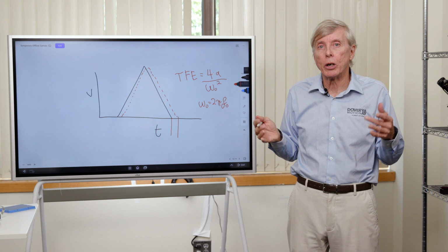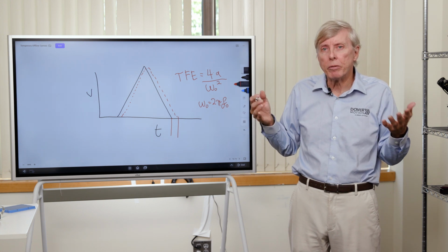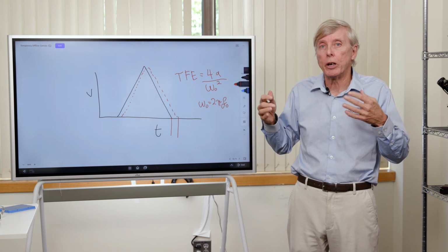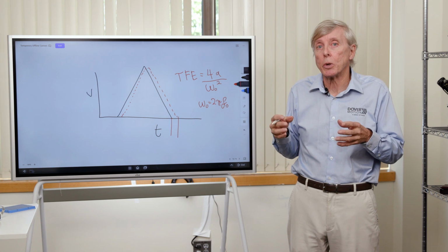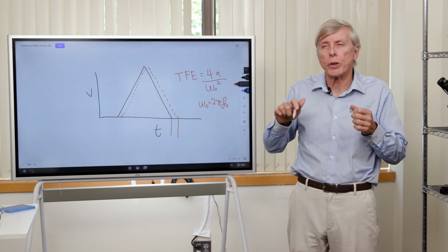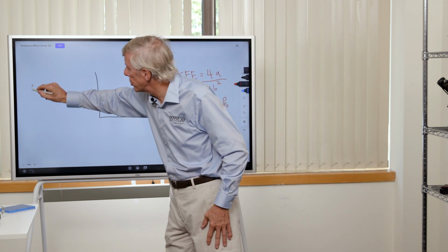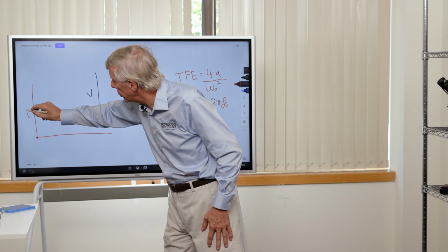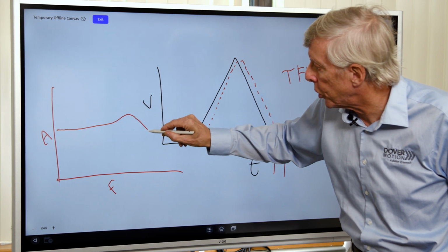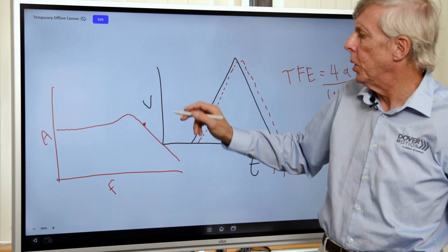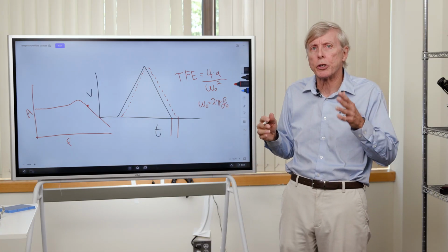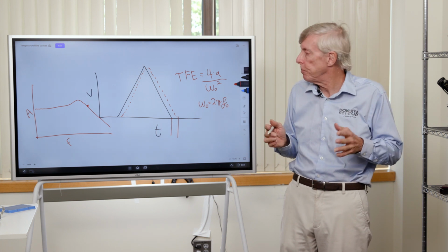This is a very important parameter of servo systems, and there are alternate descriptions of how to measure it, but typically it is when, for small signal, there is a 90-degree phase lag between the excitation and the response. And so that's the beginning of the point where the response of the system, as amplitude versus frequency, starts out flat, depending upon the damping picks up a little bit, and then drops off. So the minus 3 dB down point is another way to look at it, but we generally prefer a 90-degree phase relationship between excitation and response.